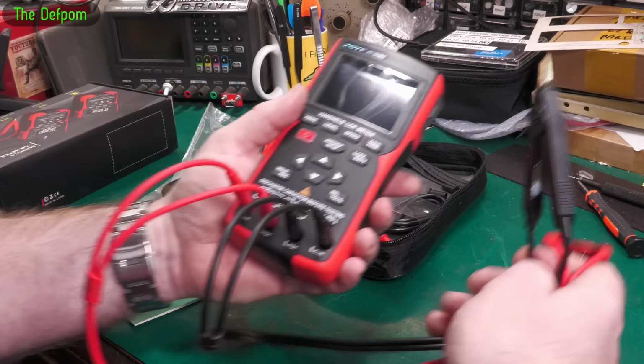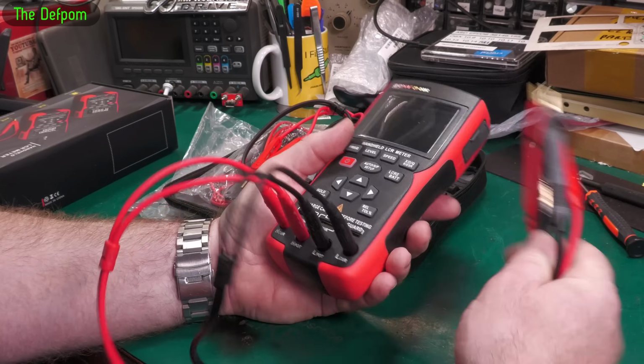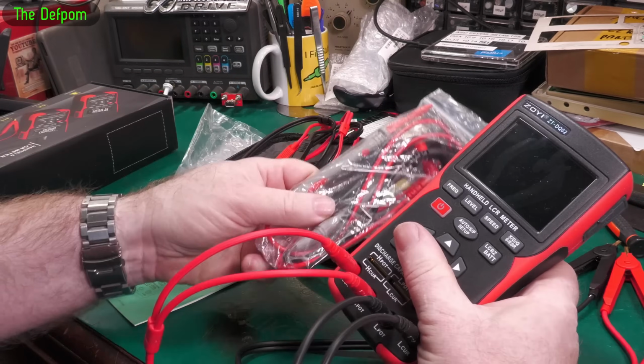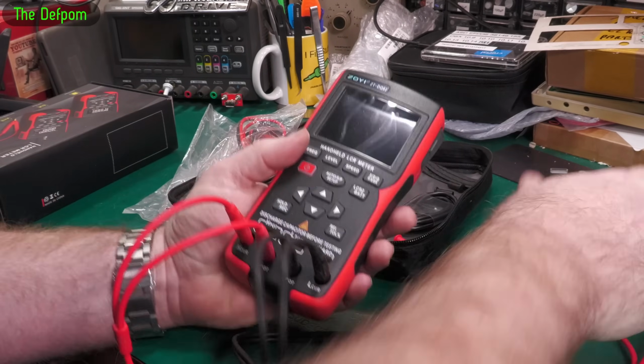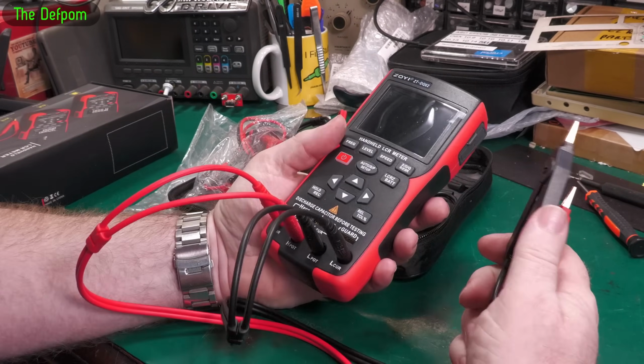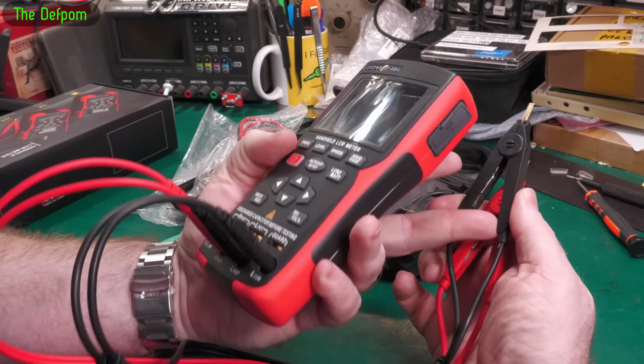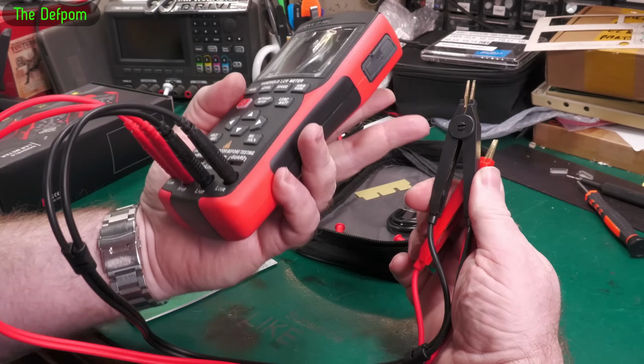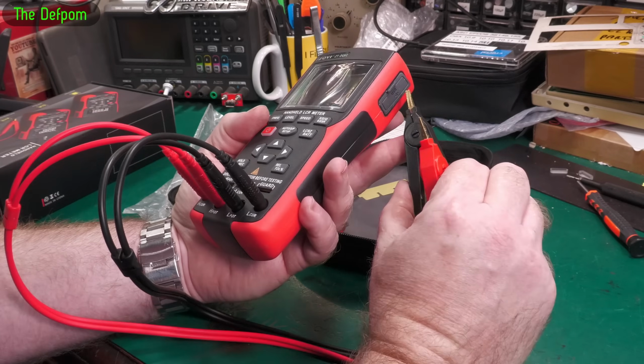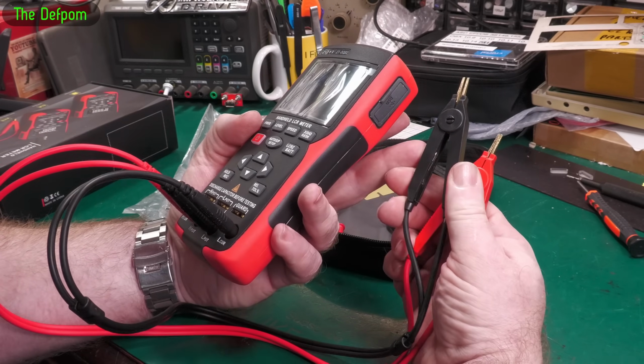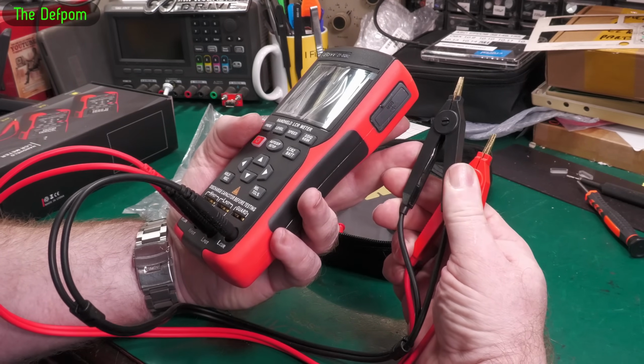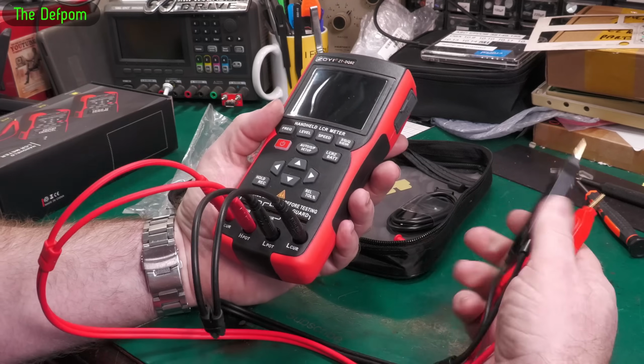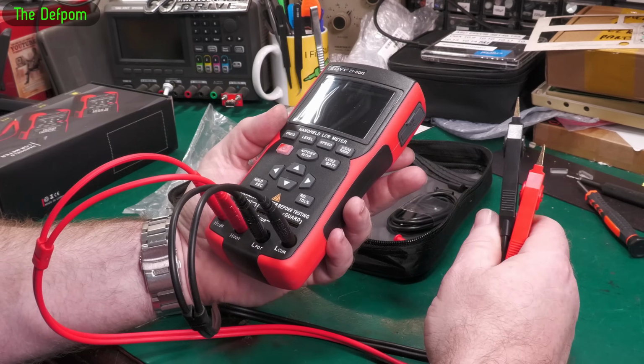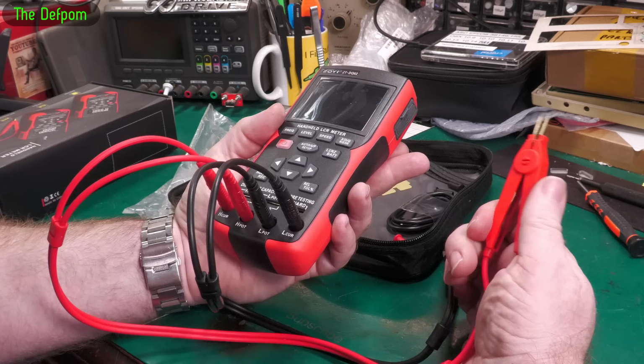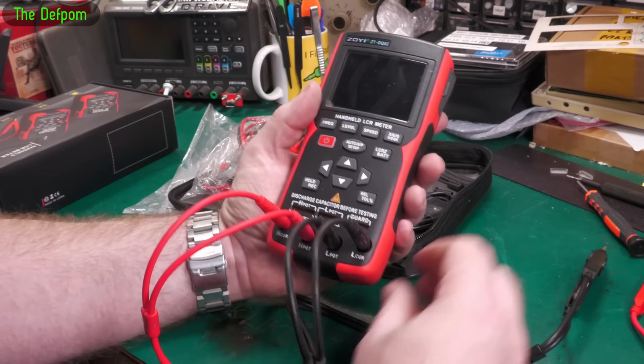The other lead we get is a proper LCR 4-wire measurement lead. So you've got the probe lead for 2-wire measurements, and this one for 4-wire measurements, and it is actually true 4-wire - each wire goes to each side of the clip. These clips are basic, I suppose, and appear to be gold plated, though they could also be brass - they look very similar. But they are at least proper 4-wire connections.